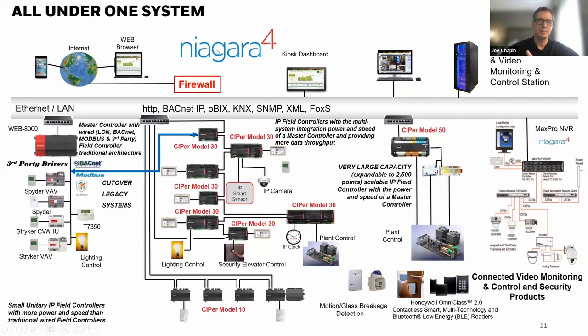Niagara, the umbrella system. So again, left-hand side is where we were. Under where it says firewalls, where we are now, the blue line indicates cutting over legacy systems. So I can do a graduated upgrade of a system, and then I don't have to do a complete slash and replace of all the cabling if I choose not to. And don't forget, we also have the T1L where I can reuse existing wiring and bump up my speed from 80 kilobits to 10 megabits. So that's a lot you can do.